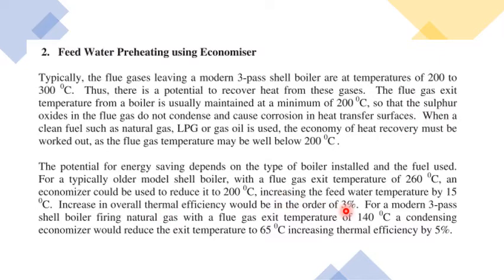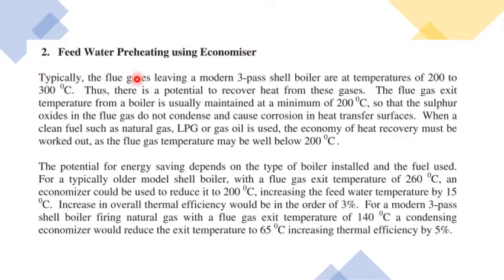As a thermal rule, if the feed water temperature is increased by 15°C, the thermal efficiency of the boiler increases by up to 3%. So using an economizer for waste heat recovery increases boiler efficiency and is an important energy-saving measure. In the exam they may ask about the function of the economizer or how preheating is done.